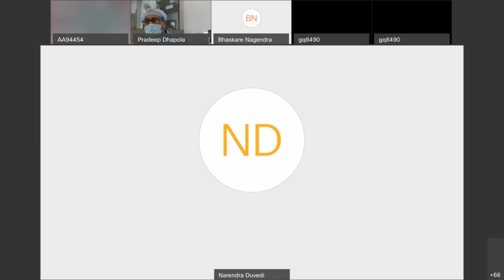Because by having a reactor in series with the capacitor, you are now giving an additional low resistance path to harmonic current than earlier. So that particular step is going to carry more harmonic current, and because of that the capacitor comes under stress and deteriorates and gets damaged early. So it is not advisable. If you want to change, you should change the reactor together with new capacitors.